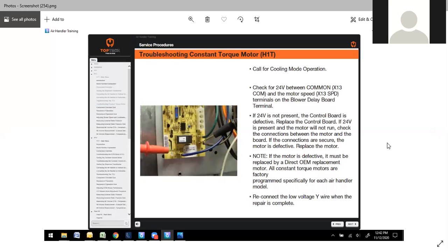So at this point, you can call for cooling mode. You're going to check for 24 volts between common, which is the X13 COM, and the motor speed X13 SPD terminals here. If 24 volts is not present, the control board is defective. Because as soon as you put it in cooling, you should get 24 volts at those two terminals. That's what actually turns on your blower. So if that's not there, replace the control board.